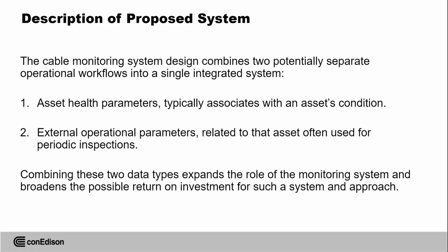And second, external operational parameters, related to what the asset is often used for: periodic inspection, vault inspections, or route patrol to see if anybody is digging or working near our system, to address security measures if somebody is trying to enter the underground vaults, and also to find a failure. If sometimes a failure happens, you need to find it.